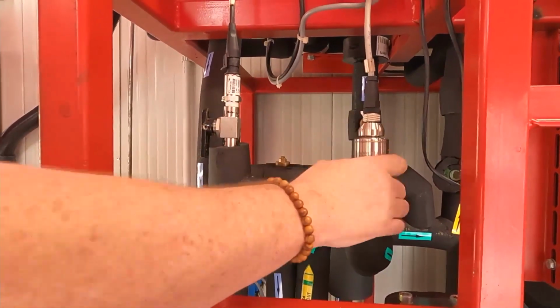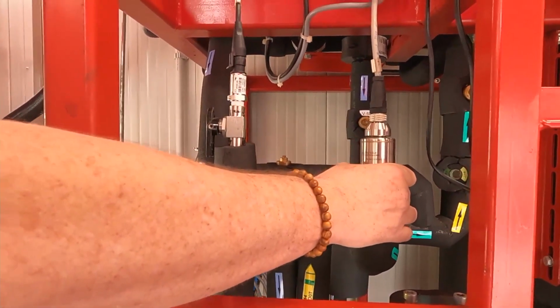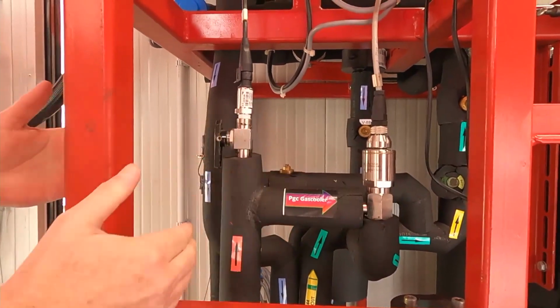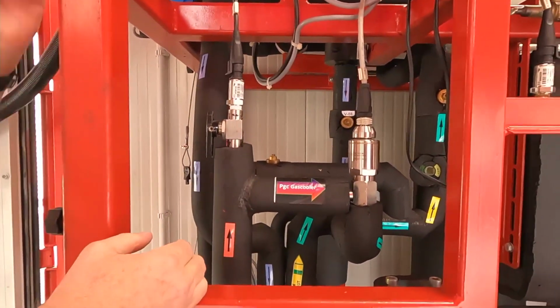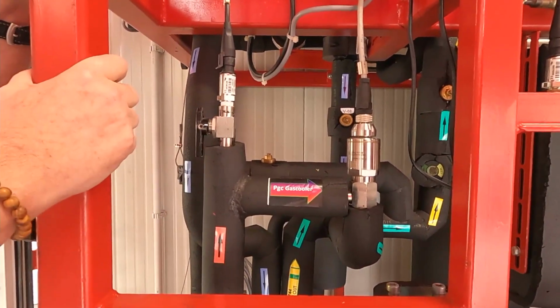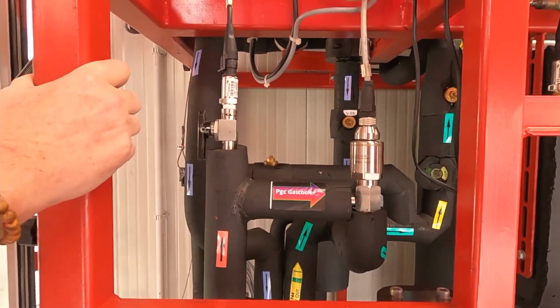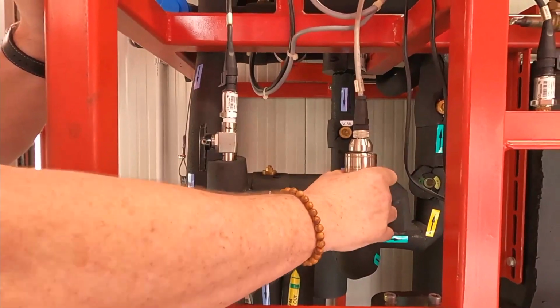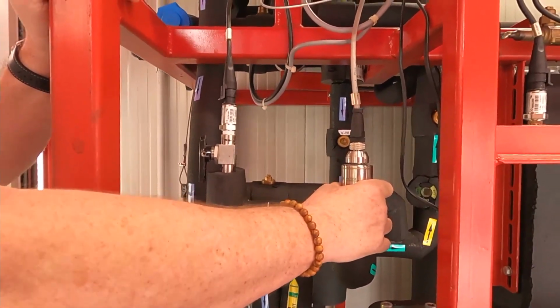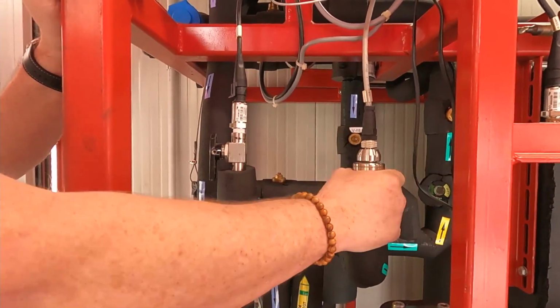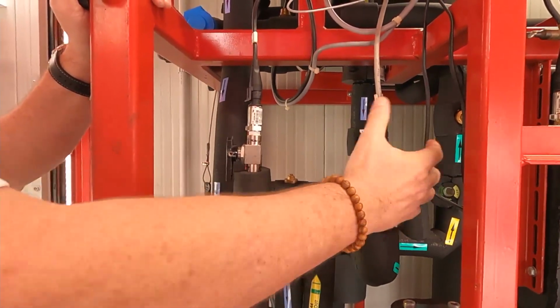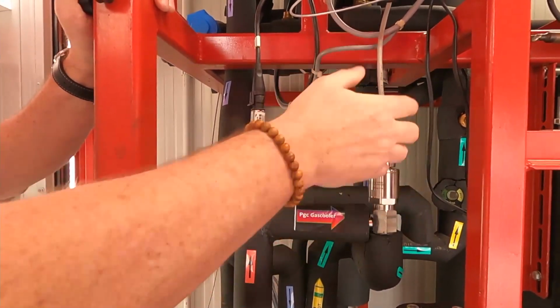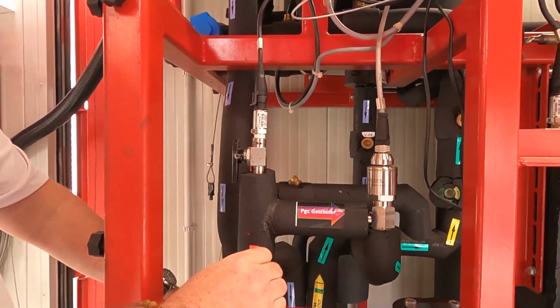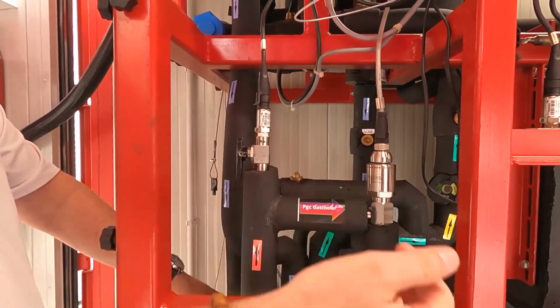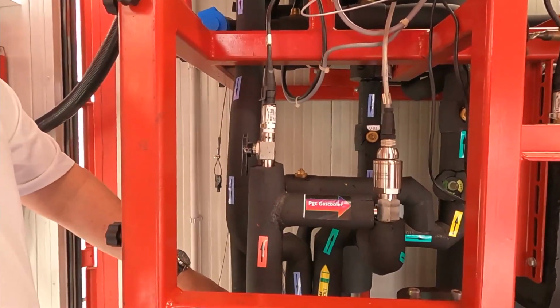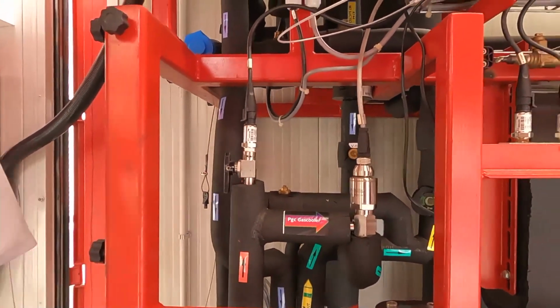There is some benefit to having both. In a low ambient condition on an ejector block, they're not equal stages through the different nozzles and ejectors, but you're only going to get maybe a combination of 15, 16 steps from the ejector block. Here you've got 2,500 steps on the high pressure valve. So for low ambient, it does kind of make sense to have the high resolution of the stepper valve. And then when you get above a certain ambient, move over to try and get your Venturi effect, pull the trigger on the pressure washer wand, pull that load up to your parallel compression temperatures. I hope that answers the question.